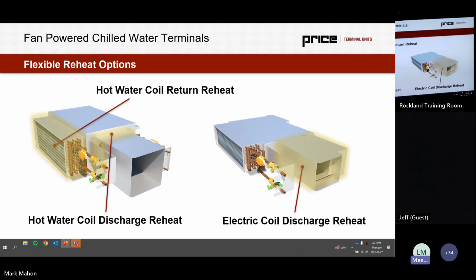So the other alternatives to use are very large coil on the return, that's much bigger, that has much longer tube runs, and that's going to allow for better capacity with lower air pressure drop. This could be a 4-pipe solution, or it could be a 6-way valve hot-cold changeover solution. Both exist, both have been utilized, both are pretty familiar and comfortable in some different markets. Now, this coil on the right is often something like 15 by 16 inches, while the side coil on the left is 18.5 by 31.5. So we're seeing more than a doubling in face area, which is going to reduce pressure drop and work a lot better for low entering water temperatures. Any questions?